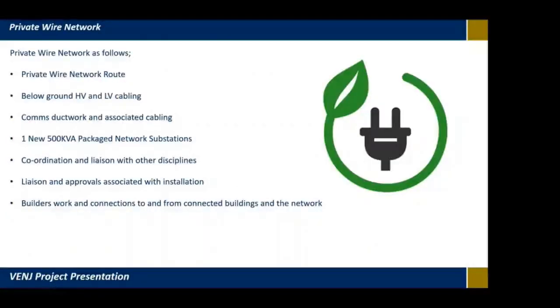In terms of the private wire network itself, the route follows the same routes as the district heating, so to keep costs down from civils and excavation, it's all within the same trench, with spacings as per NJUG and streetworks requirements. There's also comms ducts that run the length of the network for communication between the connected buildings and back to the energy centre, its metering and controls, etc.